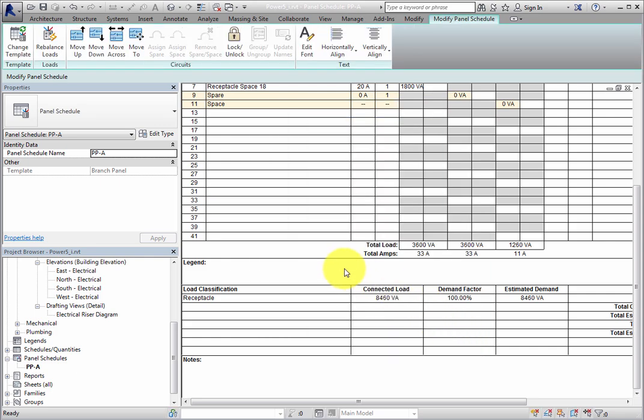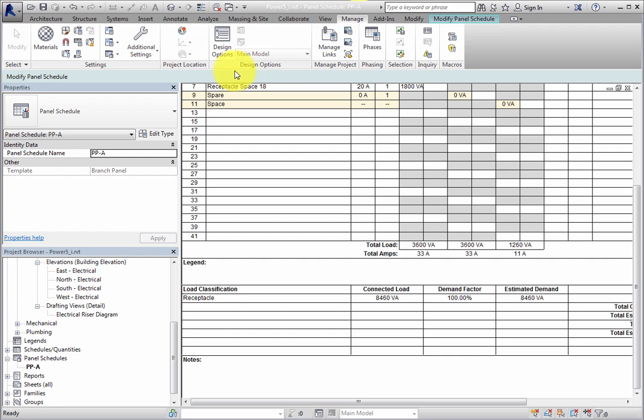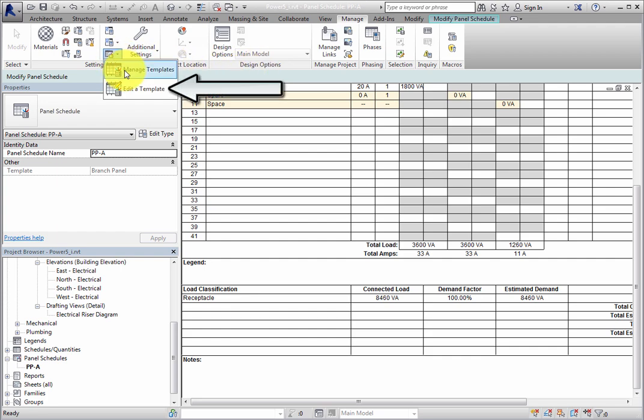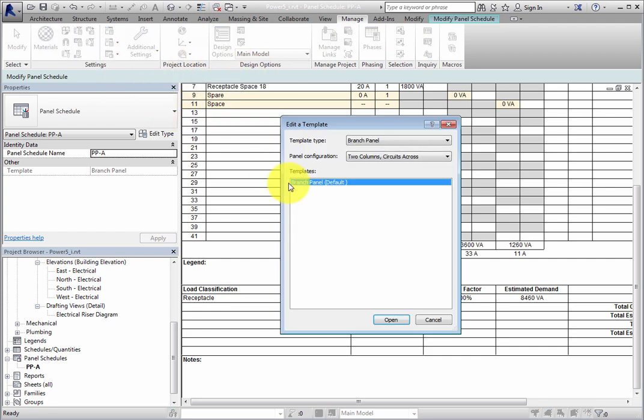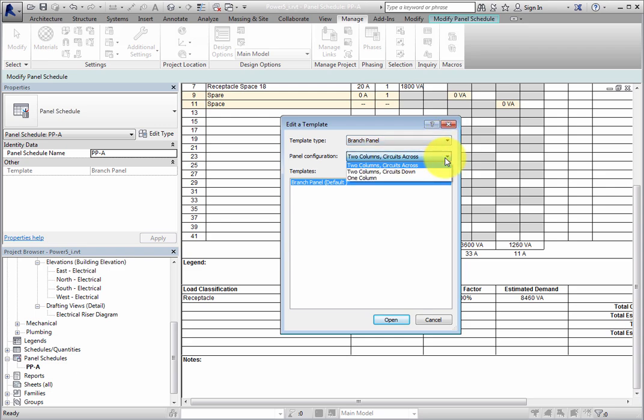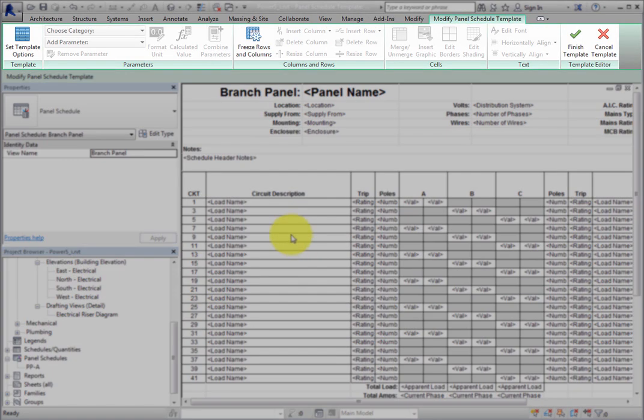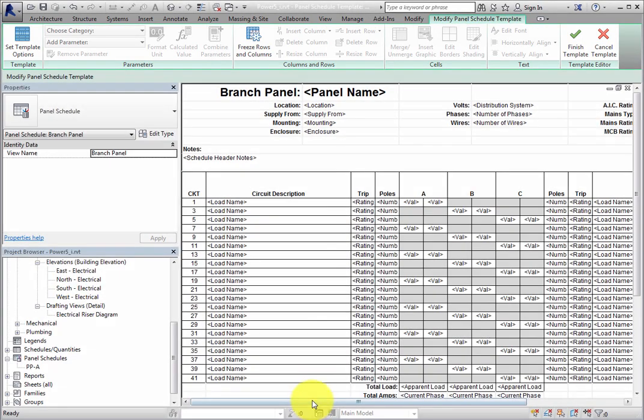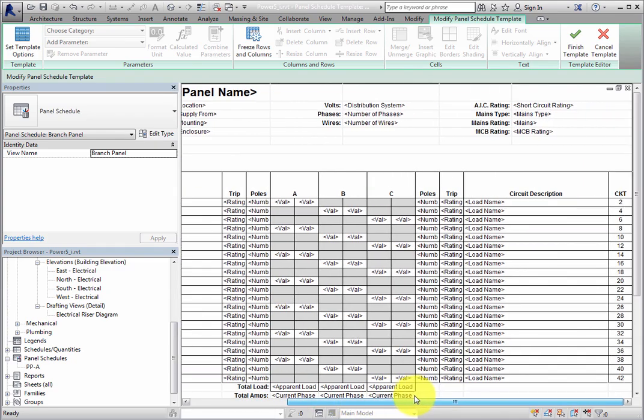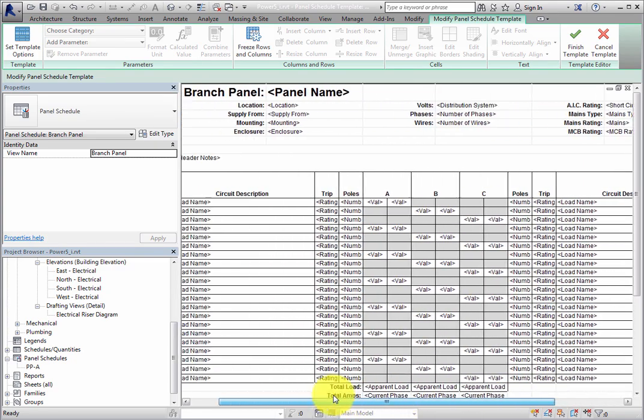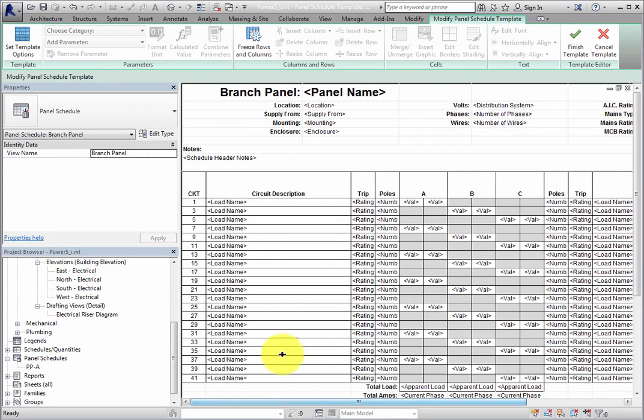Now switch back to the Manage ribbon and expand the Panel Schedule Templates dropdown. This time, click Edit a Template. Revit displays the Edit a Template dialog. Once again, you can filter the templates by Type and Panel Configuration. Then when you select a template in the list, you can click Open. Revit then goes into Modify Panel Schedule Template mode. You can use any of the tools available here to modify the Panel Schedule template. When you are finished editing the template, click Finish Template.